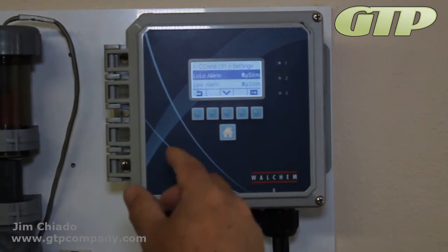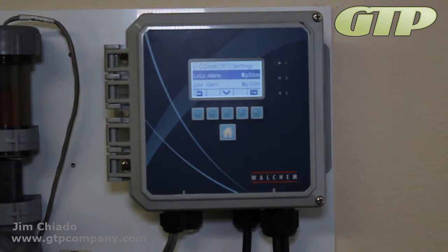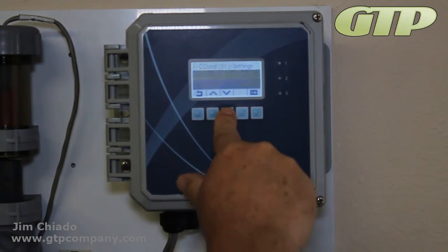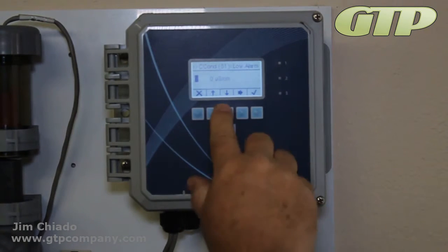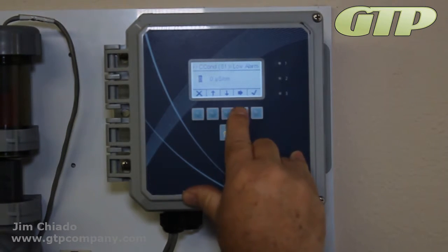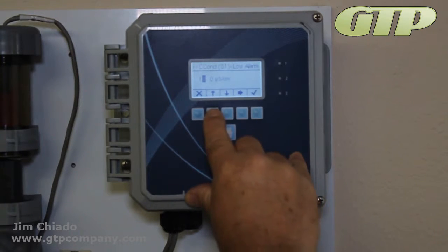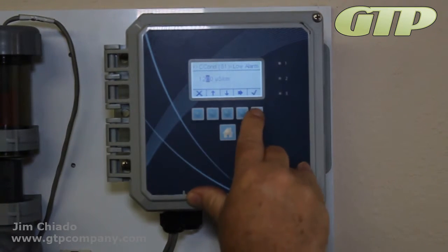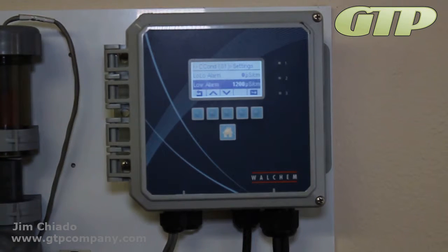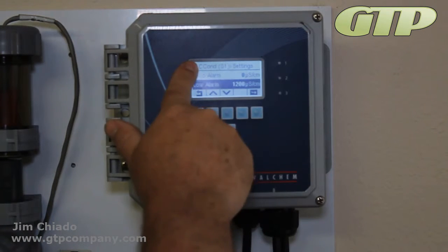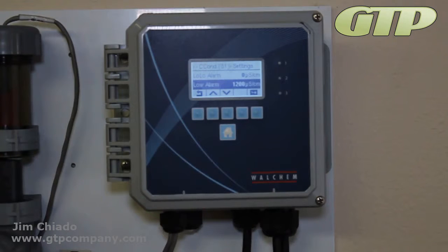If you operate in the 2,000 range, your low alarm on your incoming water, say, at 600, 800. Maybe you want to set this at 1200. You know that the valve is open if it ever reaches 1200. So we're going to come in here and set that at 1200. We're going to arrow key over, up, 12, up, 1200. So normally this thing functions at about the 1500, 1200 range. If it ever gets to 1200 or below that, this alarm will go off. It'll reach up here at the top on the home screen, and at least somebody will be notified that it's stuck in a bleed cycle or something's going wrong.